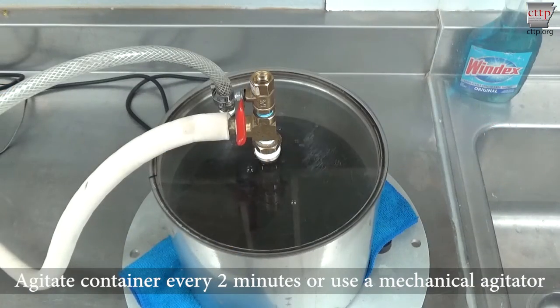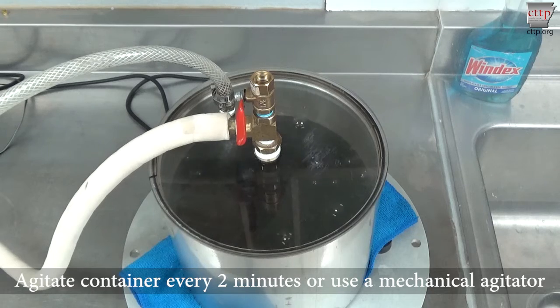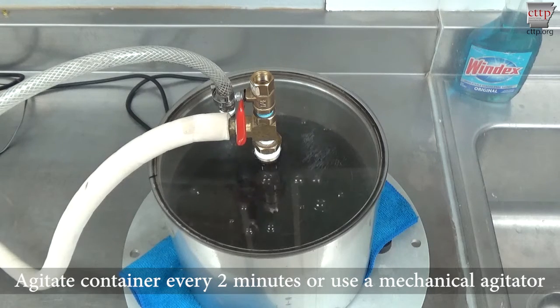Agitate the container every 2 minutes or use a mechanical agitator. The water may appear to boil under initial vacuum.